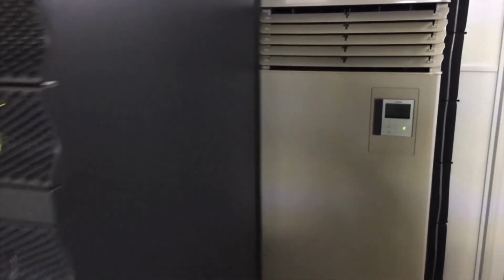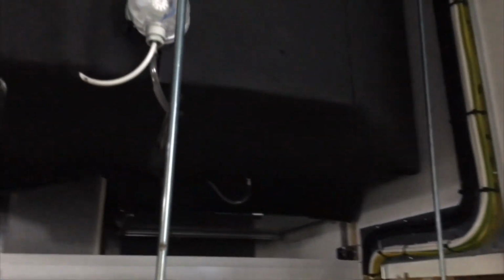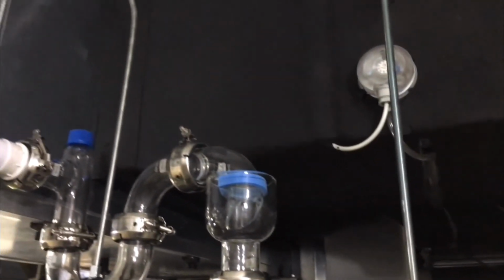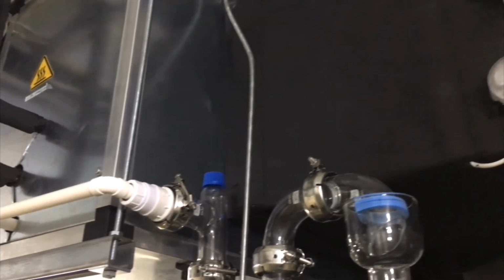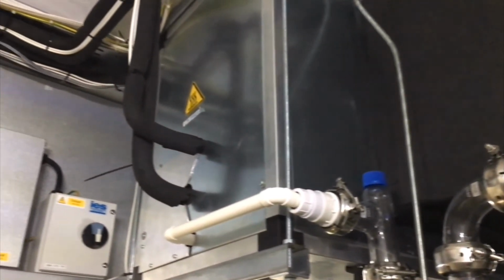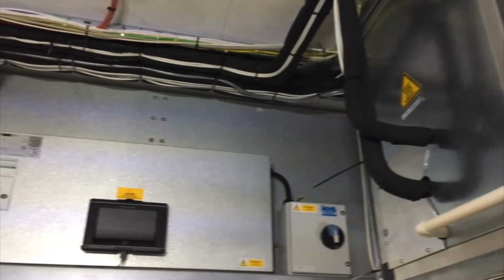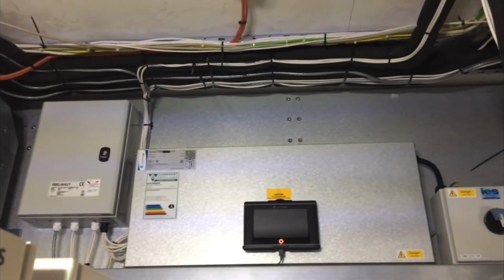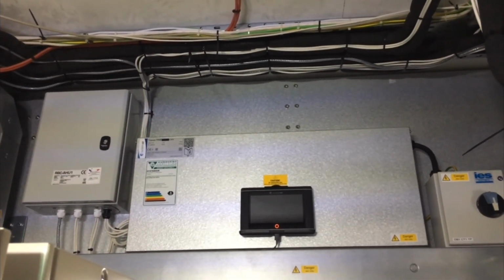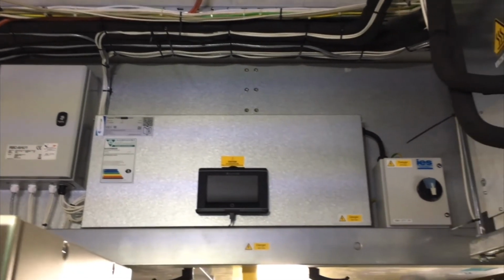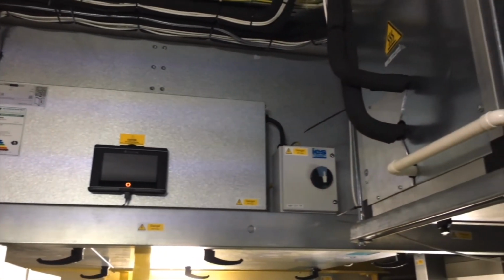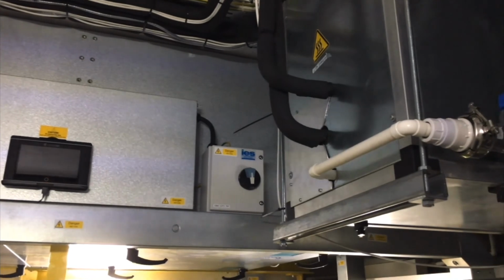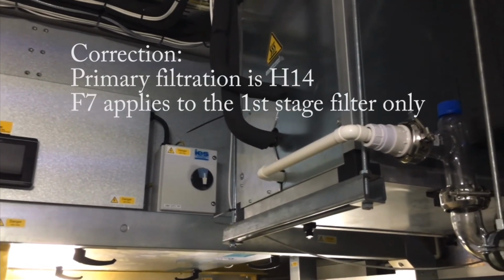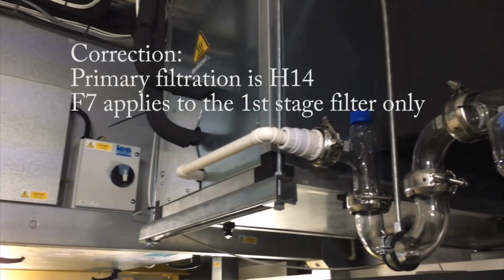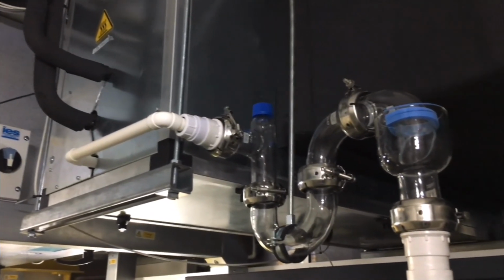And if I just turn round here, this, tucked away but very large in the ceiling, is the main air handling unit. This system is designed to provide 25 air changes per hour with positive overpressure and F7 filtration, as per common specifications for cath labs.